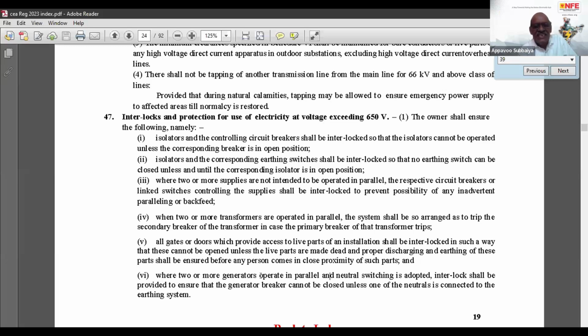So these are the logic. This becomes a very cumbersome task in actual execution. Failure of neutral opening and such things occur. So the regulation says it is not mandatory. If you prefer neutral switching, you adopt these measures. Otherwise, when two or more generators are there, you can adopt IS 3043 and 732 circuits, which are already there. That is single point earthing. People hesitate to provide single point earthing, which gives a common reference and will avoid many flaws in the downstream installations. And that's what we can infer from this interlock.